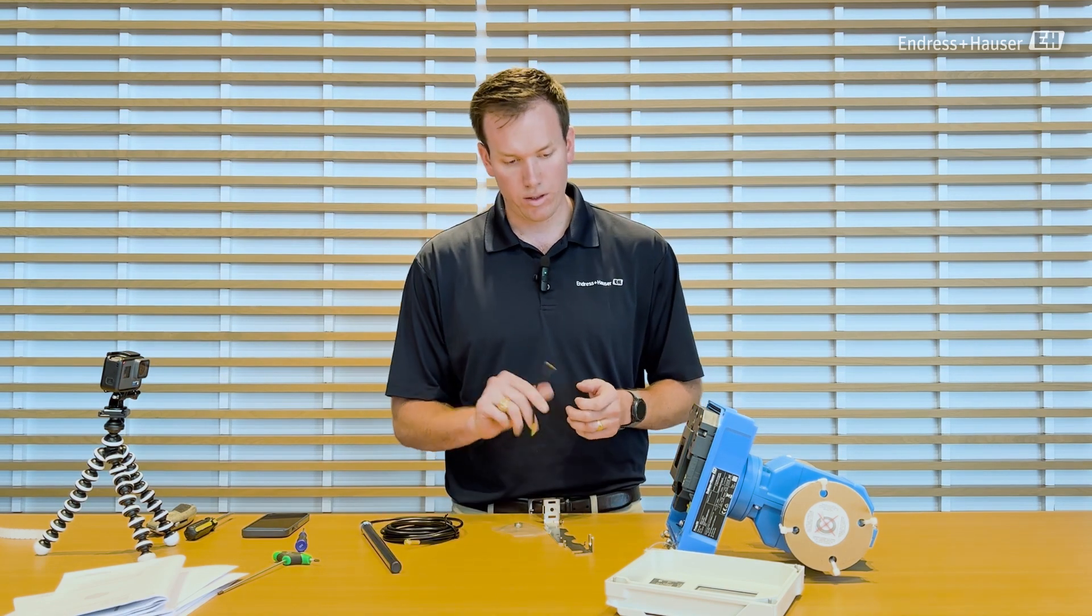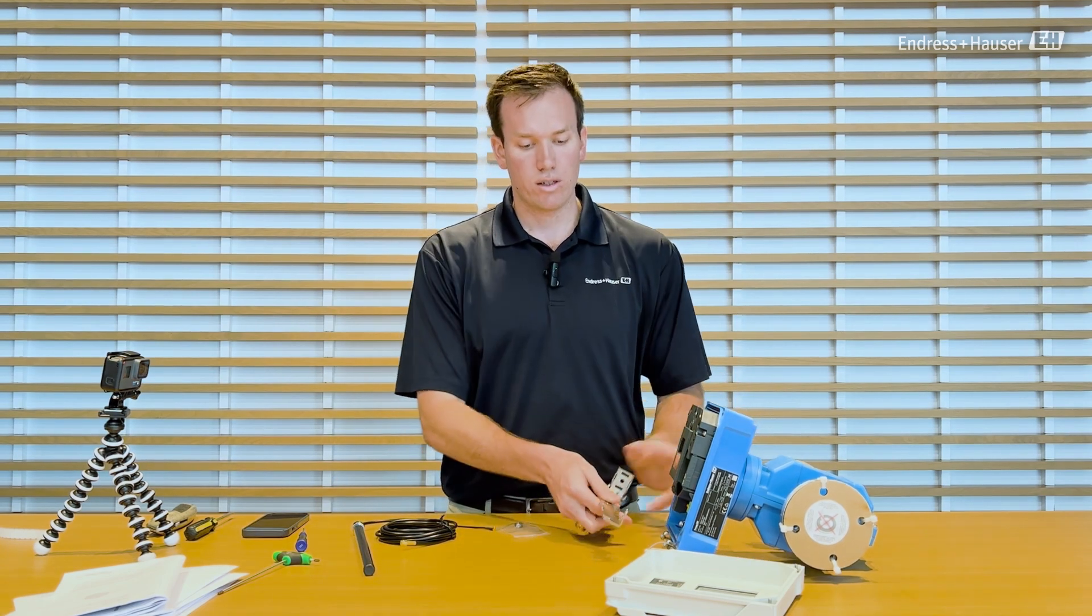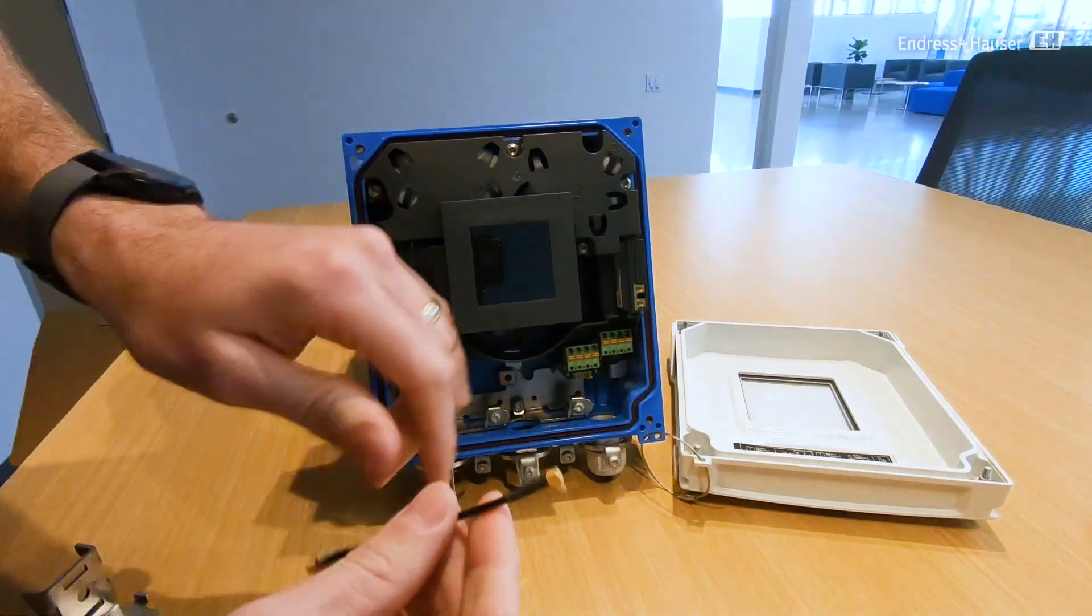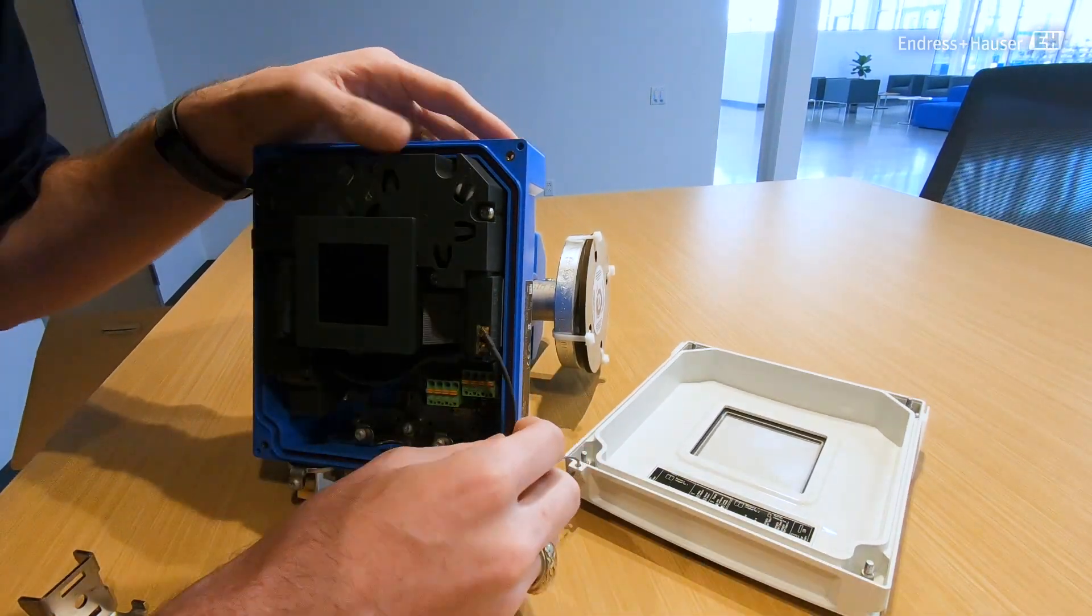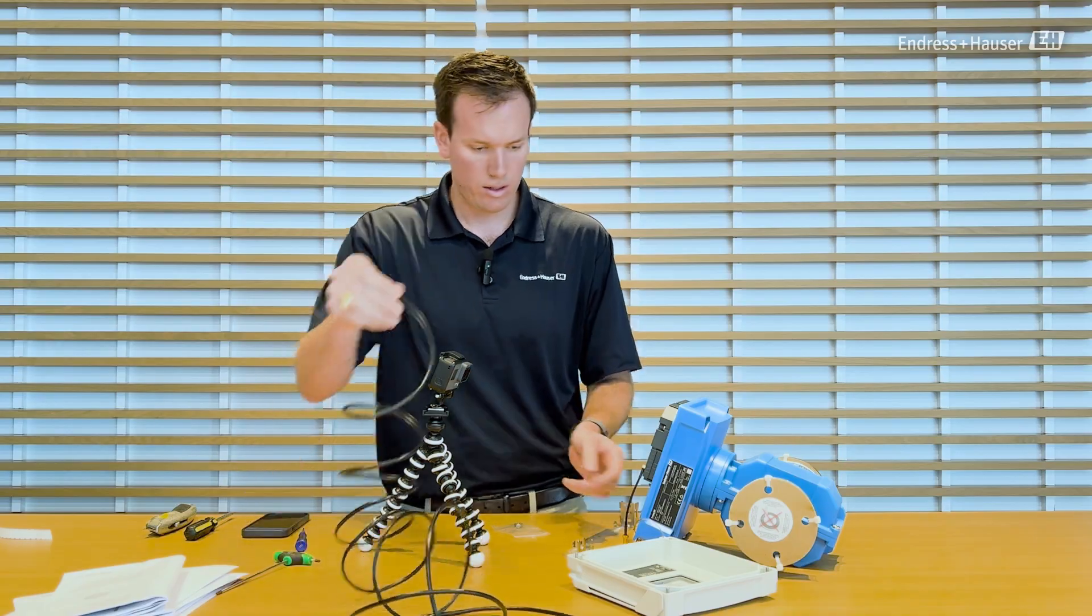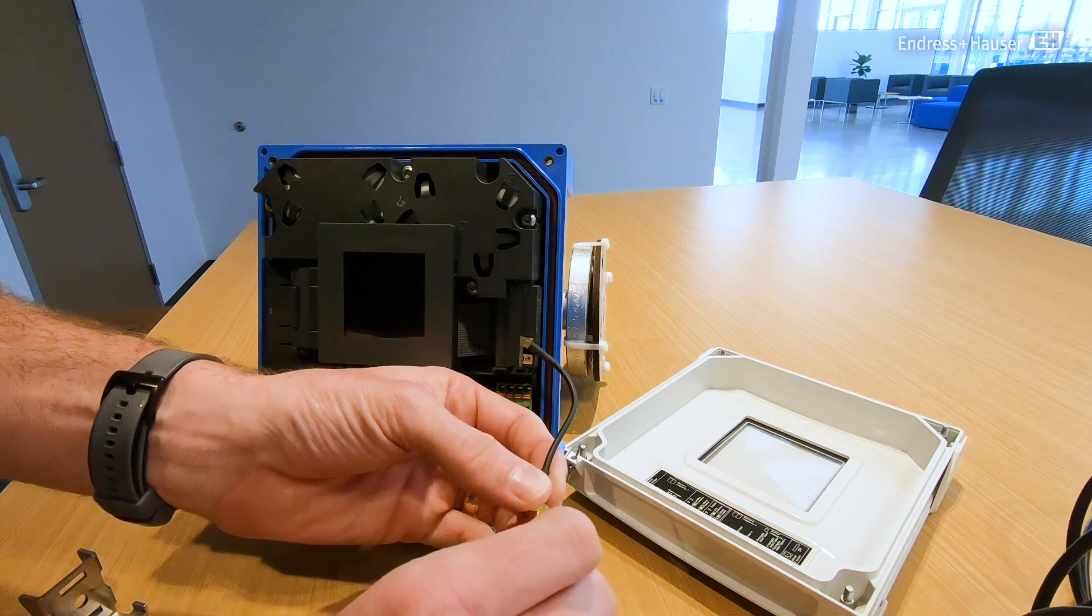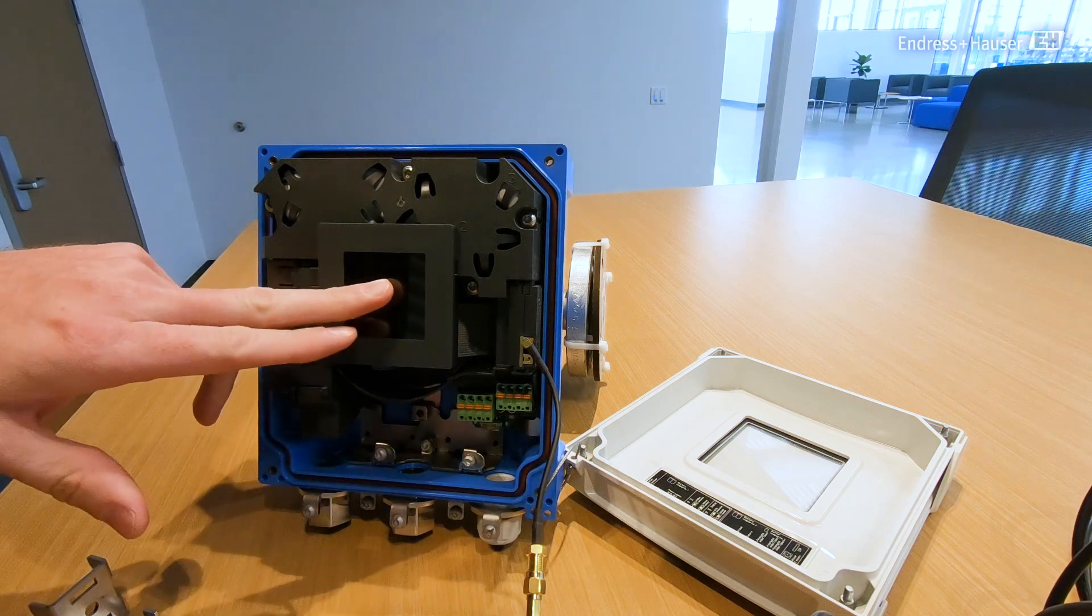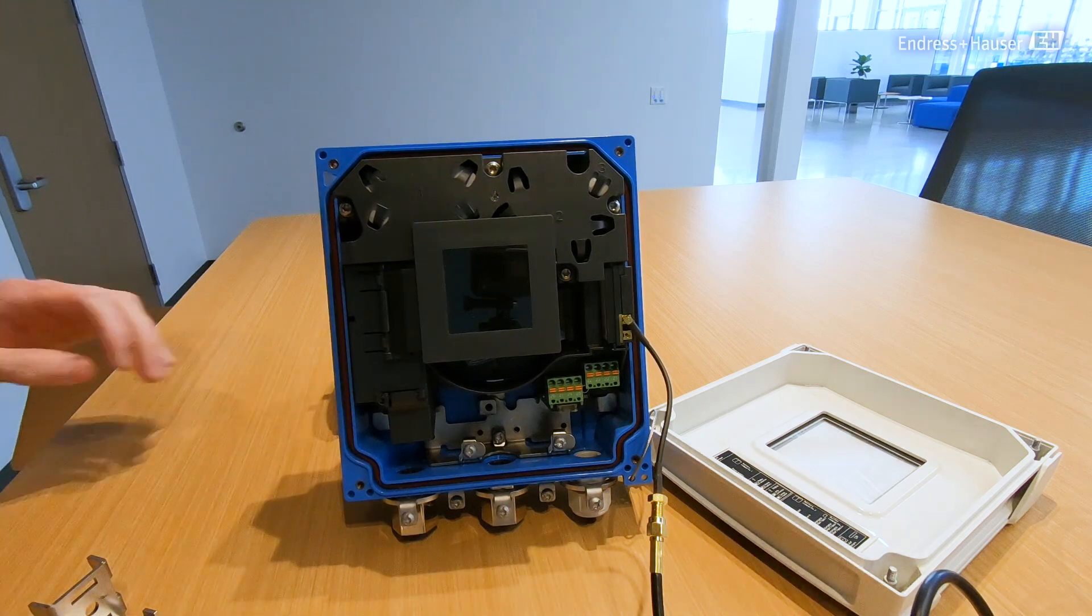Comes with a couple components. So here's the main connecting cable for the antenna. Grounding plate. This is a polycarbonate housing, so to make sure that antenna is properly grounded. And then the antenna itself. So this antenna plugs in right here, this antenna slot. So I'm going to plug it into antenna slot number one. And for now I'm going to just leave the antenna out. I'll hook up the grounding plate later when I actually go to install this meter. Hook up the antenna there. And this meter is ready to be installed.